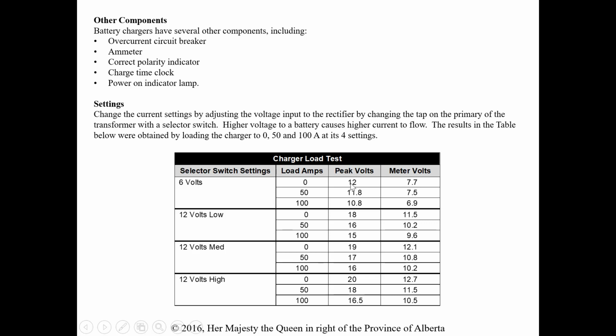So this is the peak of the secondary, and the meter would read VDC. This is the DC output. Okay. So again, higher voltage causes higher current to flow. The results in the table below are obtained by loading the charger to 0, 50, and 100 amps at its 4 settings. Okay, so again, just to look at some of this stuff here so that we can see what some of these numbers are doing. We have our peak volts, and then we use that percentage, 63.7%, and that's going to give us this expected VDC. So we're just multiplying the peak by that percentage, and we're getting this expected VDC output based on the peak volts.